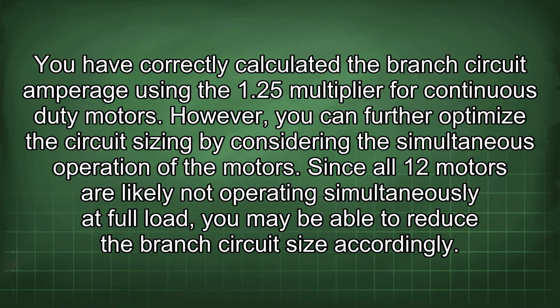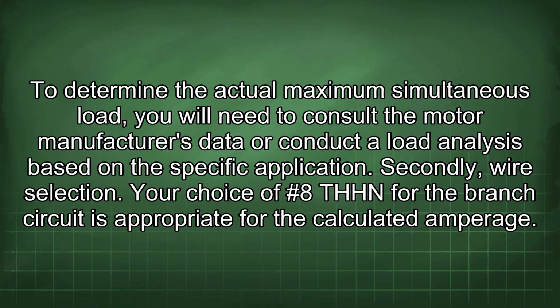However, you can further optimize the circuit sizing by considering the simultaneous operation of the motors. Since all 12 motors are likely not operating simultaneously at full load, you may be able to reduce the branch circuit size accordingly. To determine the actual maximum simultaneous load, you will need to consult the motor manufacturer's data or conduct a load analysis based on the specific application.